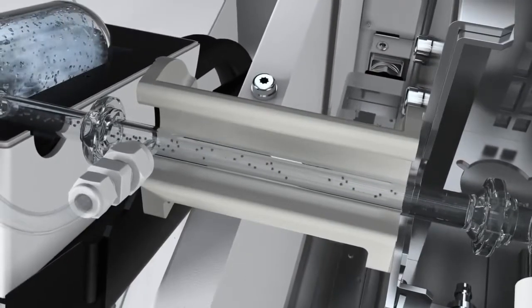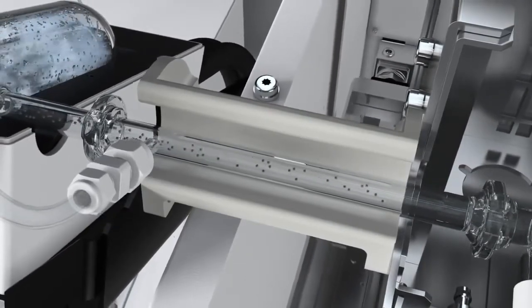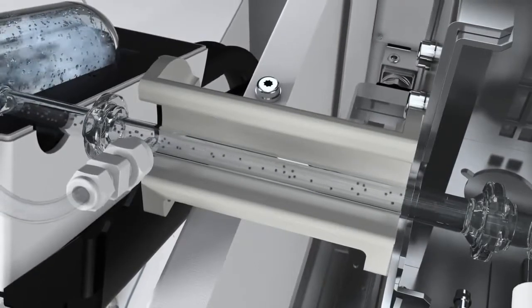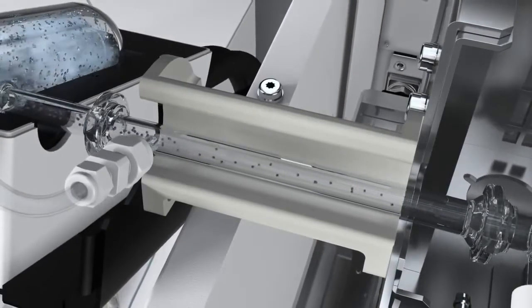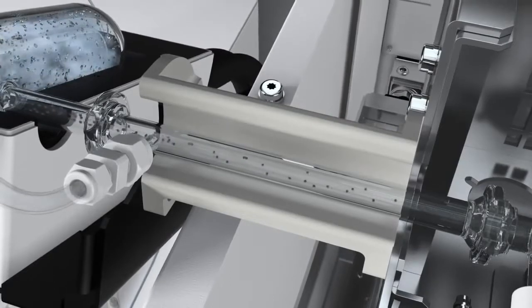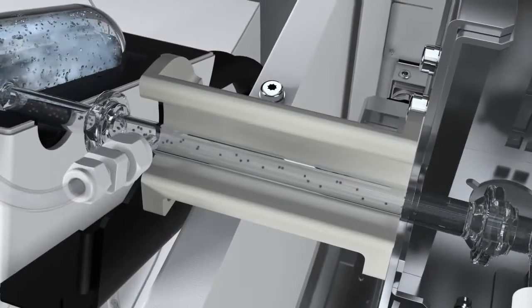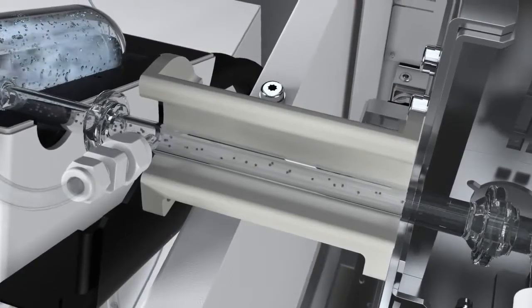HMI's aerosol dilution also reduces oxide levels by a factor of 10 to around 0.1%, which virtually eliminates matrix suppression and allows highly variable samples to be measured accurately against simple aqueous standards.